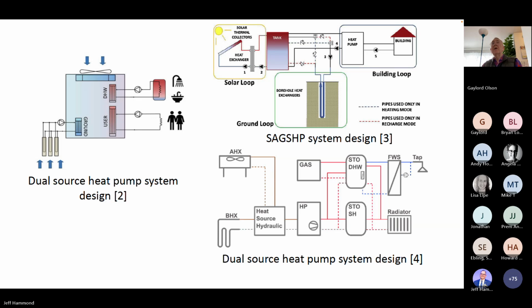Reference number 3 is an example of what we'd call a level 3 — it's reference number 3, but in terms of the 4 levels defined earlier, it's also level 3, because they can have an either-or choice. They've got boreholes and solar thermal collection. With the valves and pumps they show, you can have either the boreholes by themselves feeding to that heat pump, or the solar thermal by itself feeding to that heat pump. That would be what we're calling level 1. They can also do preconditioning from the solar thermal into the ground loop — that's what we're calling level 2.